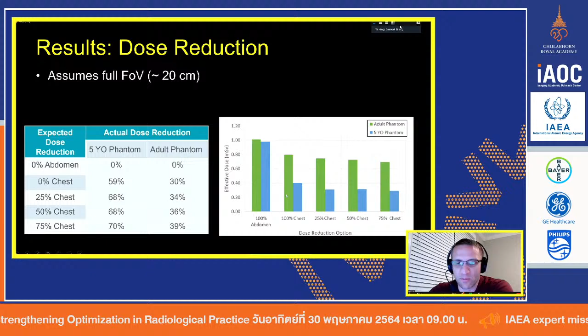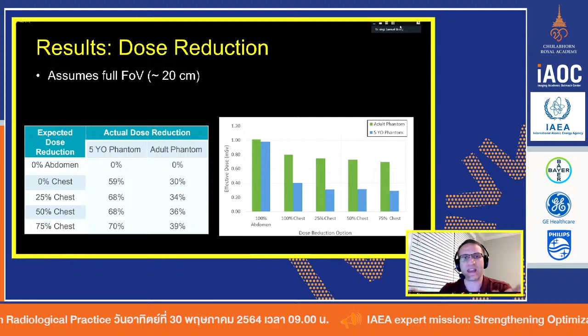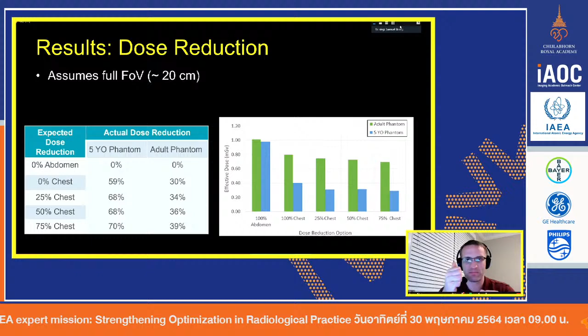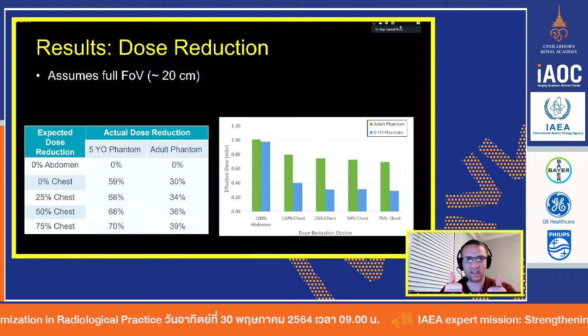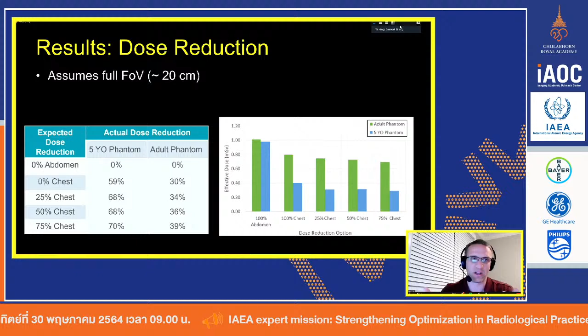The only reason I bring this up is that we're starting to do a lot more CBCT. I believe the whole field of interventional fluoro is moving this way. We've come to that tipping point where we need to start asking the vendors to produce low dose, better optimized protocols for routine use of CBCT. 20 years ago, we were imaging kids and adults roughly the same in traditional CT. There were really no considerations for pediatric imaging. And then obviously we realized that we were overdosing kids by 4 or 5 times as much.